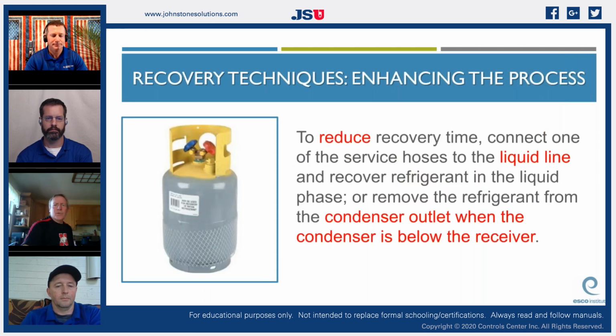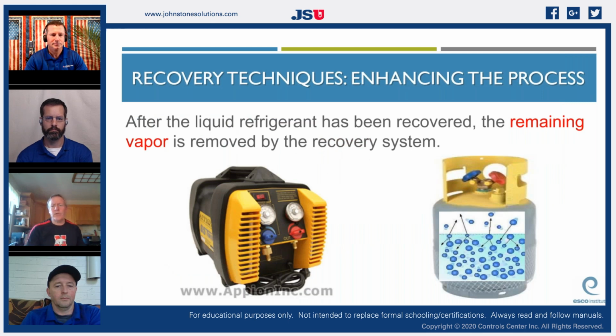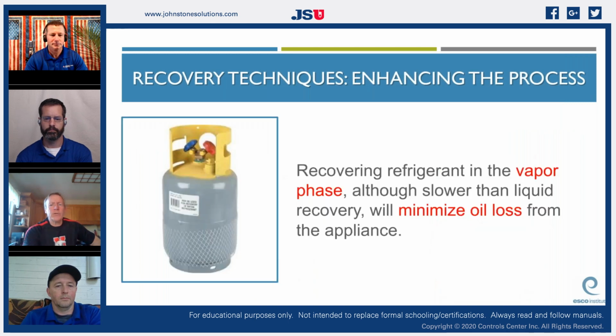Yep. To reduce recovery time, connect one of the service hoses to the liquid line and recover in the liquid phase. This is a practice we almost always did on the residential side. We would pull liquid first to speed the process up, and then we would pull vapor, so we'd get it all out of there, or at least down as far as we could. Vapor takes a lot longer, but you're not going to pull as much oil out. One of the dangers when you pull liquid is that you're going to reduce the amount of oil inside the system and also push it through your recovery tank.